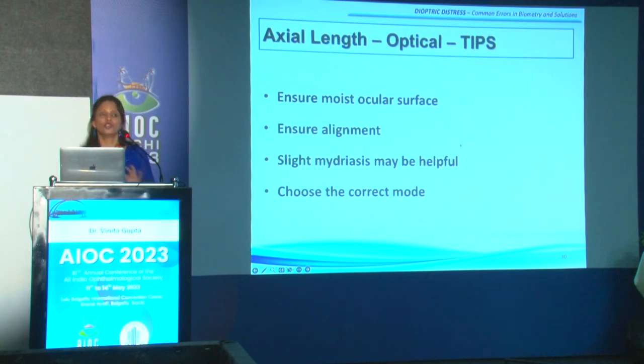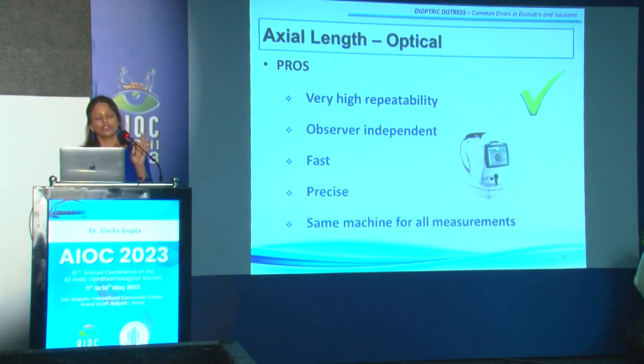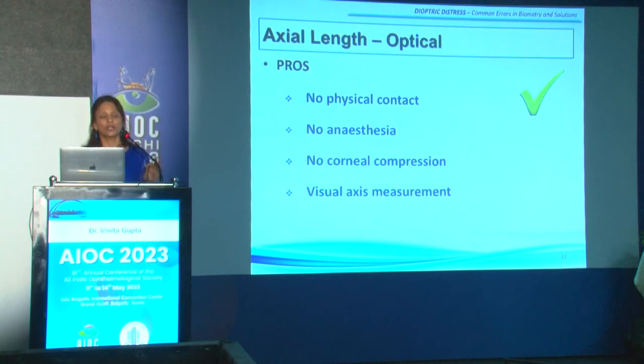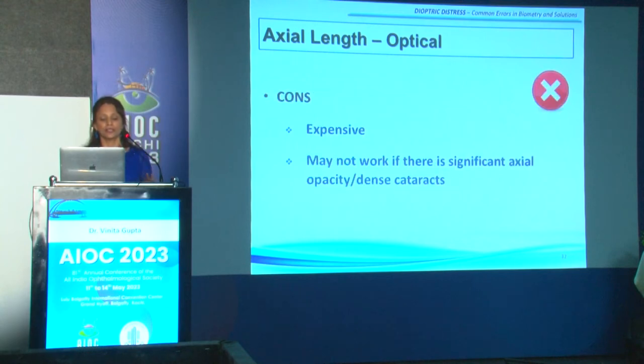The tips for this are ensuring a moist ocular surface, ensuring alignment, a slight mydriasis, which may be helpful especially in cases of PSCs, and choosing the correct mode. The advantages of this machine are very high reliability, observer independence, speed and precision, and the same machine can give you various measurements which are required as input parameters. There's no physical contact, no anesthesia, no corneal compression, and you're measuring exactly along the visual axis. The only disadvantage is it's expensive and it may not work in cases of total cataracts or significant axial opacities. Now the swept source OCTs do work in most cases.